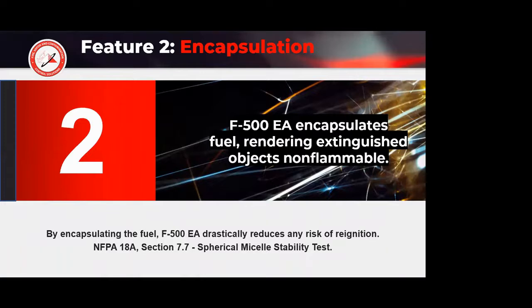So the heat reduction capability of F500 is 6 to 10 times greater than plain water, depending on droplet size, and somewhere in the neighborhood of 10 to 20 times greater than foam. And we'll address that later on in the presentation. The F500 encapsulates fuels, rendering them non-flammable, non-ignitable, and non-explosive. So there's a test in NFPA 18A, section 7.7, called Spherical Micelle Stability Test. While UL 162 is a foam qualification test, now we have NFPA 18A section 7.7 as an Encapsulator Technology qualification test. So we'll talk about that as we move forward.